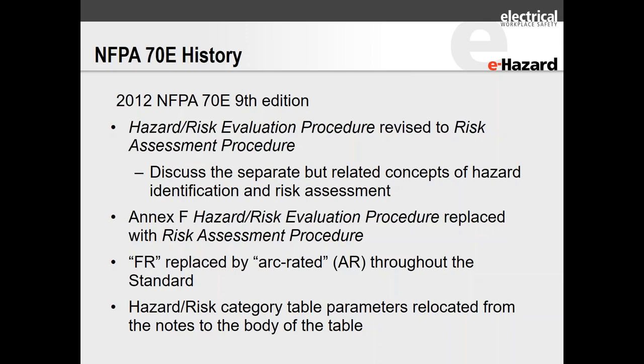The 2012 edition also introduced a discussion of the separate but related concepts of hazard identification and risk assessment. The concept of FR was replaced by AR throughout the standard. Most people in industrial, commercial, and tech worlds are happy to use the word AR. People in the high-voltage power line trade still often use FR because they used it for a long time. All AR is FR, but not all FR is AR — and we'll see the difference when we get to the PPE portion.